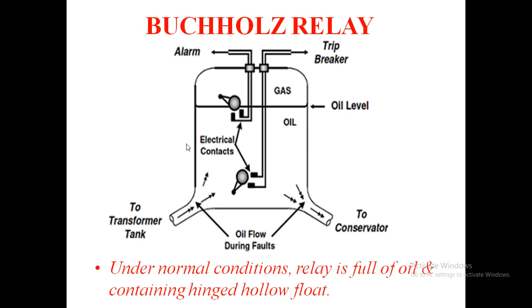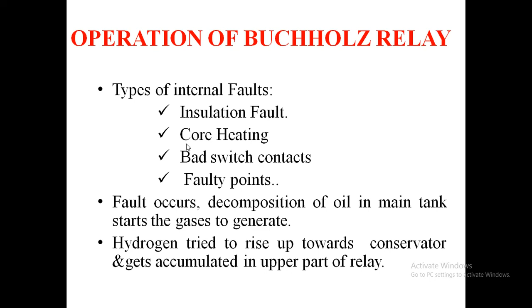The main operation of this relay concerns some types of internal fault: insulation failure, core heating, bad switch contact, faulty joints. When the fault occurs, decomposition of oil in the main tank starts and gases are generated. Hydrogen tries to rise up towards the conservator and gets accumulated in the upper part of the relay.